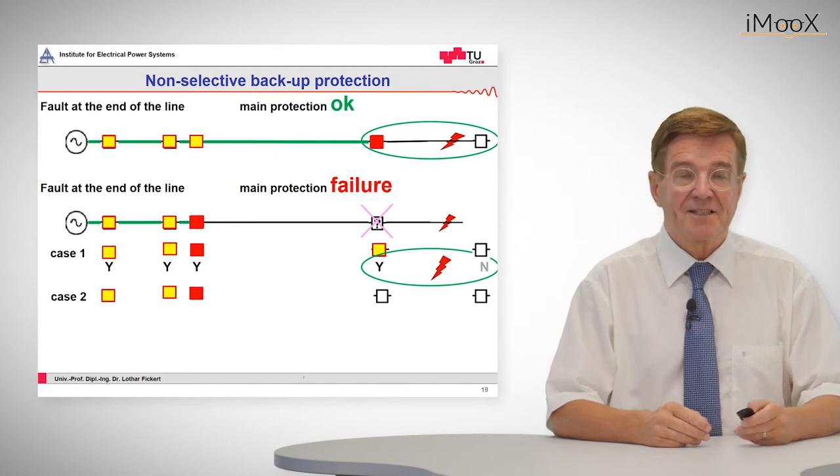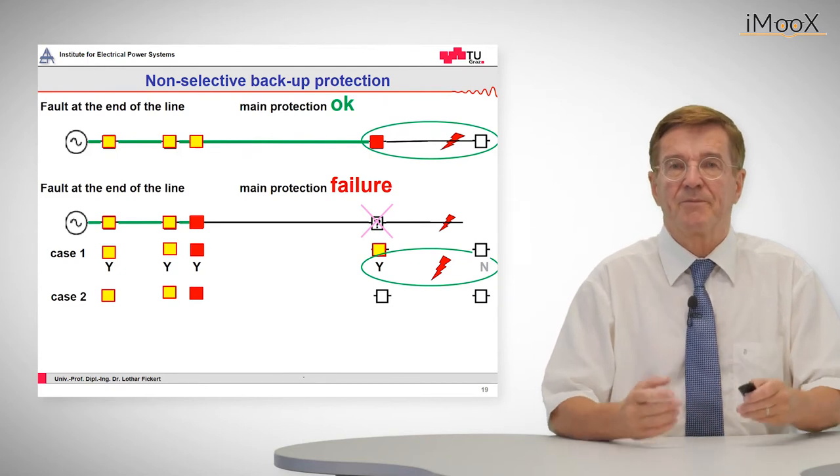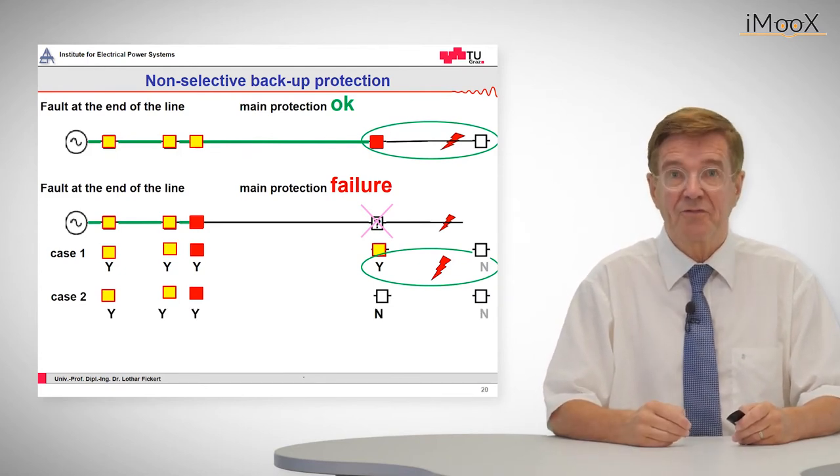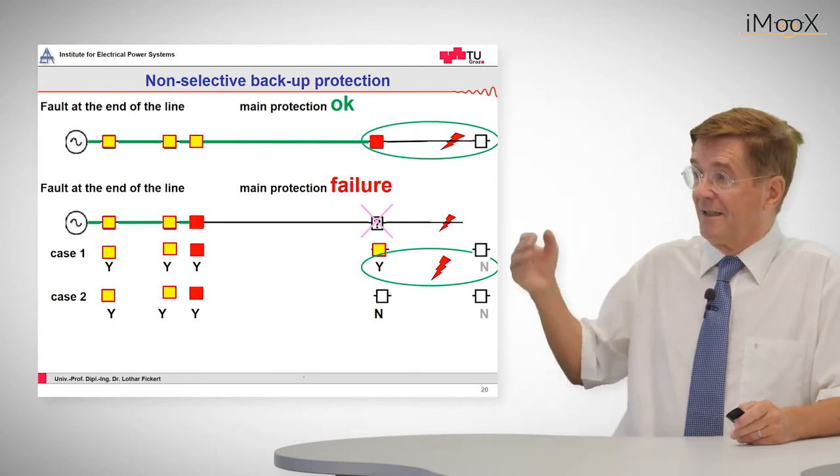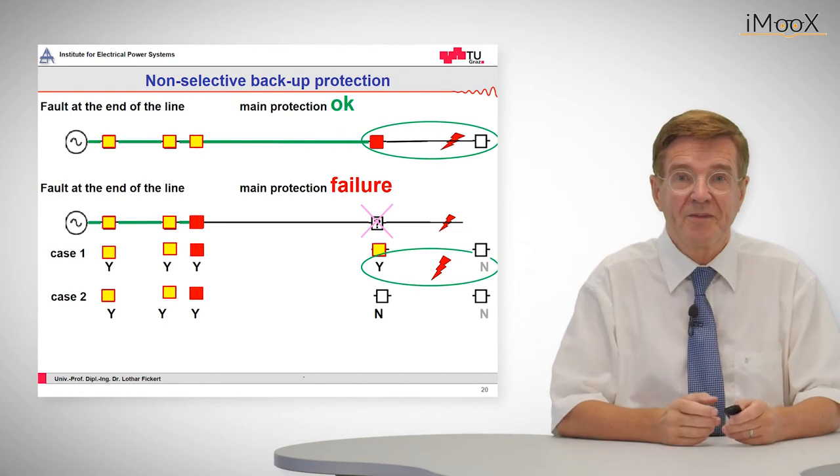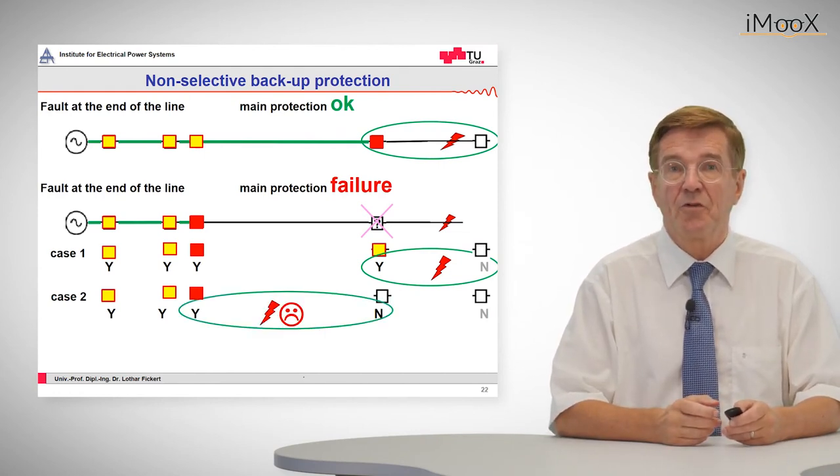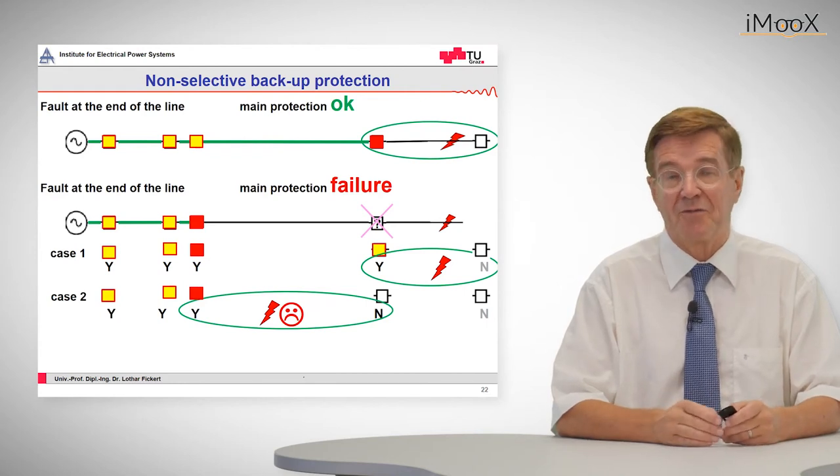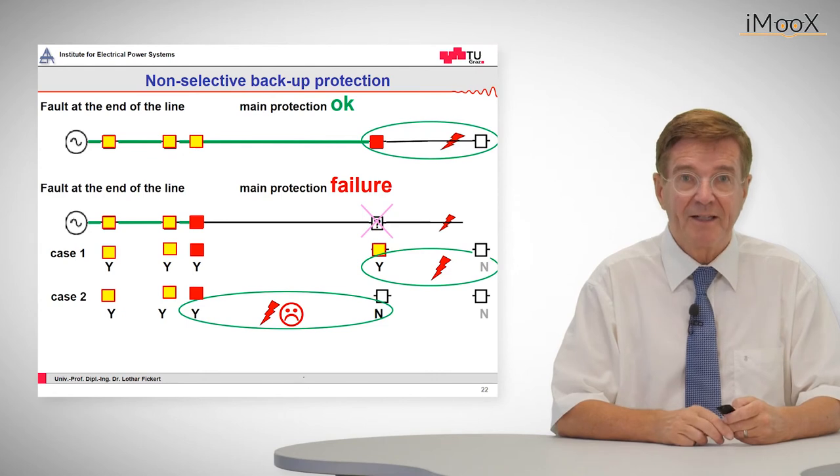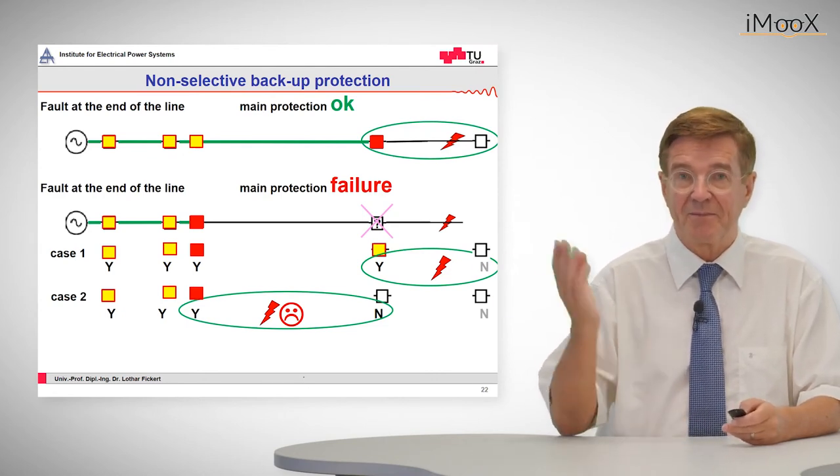The next may be case two where the relay does not react at all. There is no indication, no pick up, nothing. So in this case we have an indication for the control room like pick up, pick up, trip and nothing. From this it will be concluded by the operations people that the fault must be upstream of the last relay and that the fault should be in a section where it is not. Which is a wrong conclusion but which is correct by means of the indication.